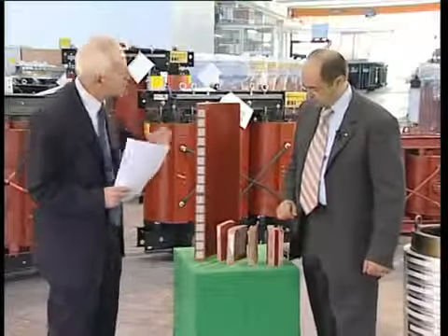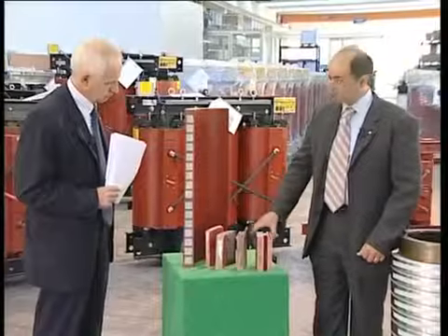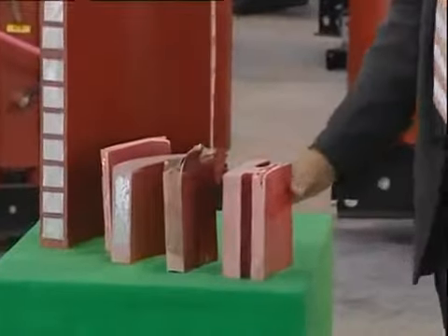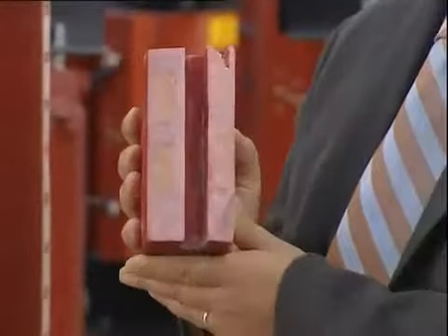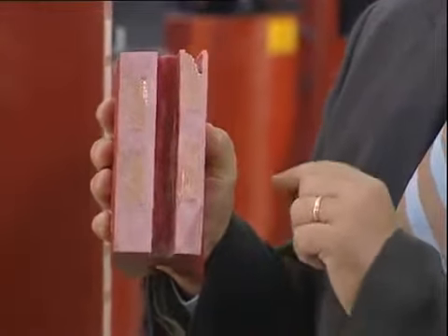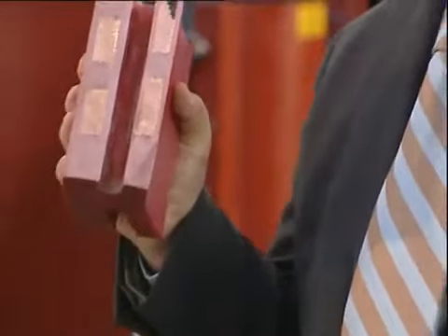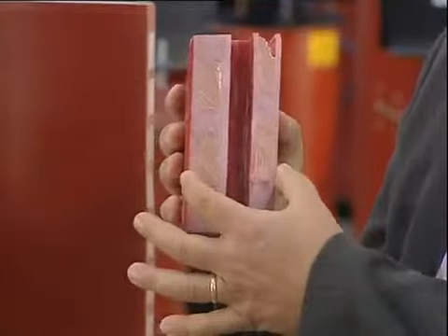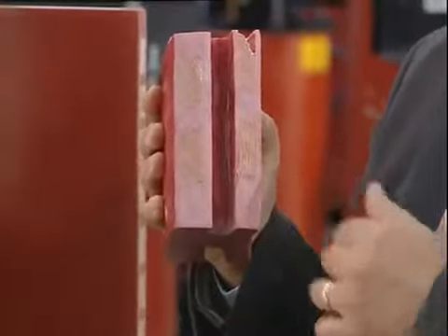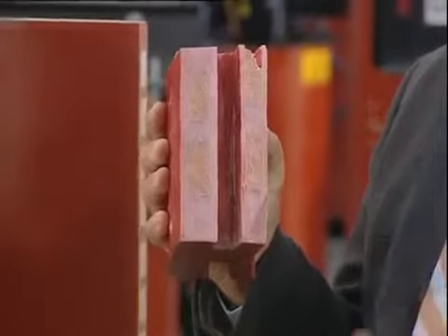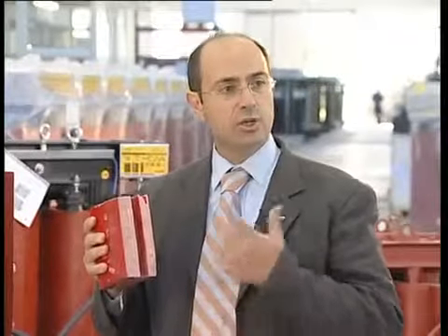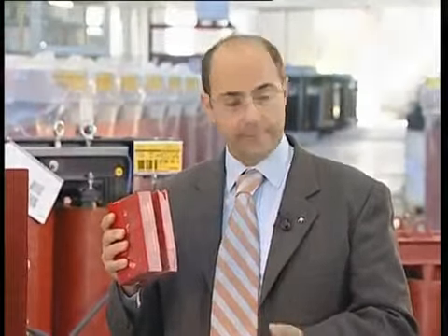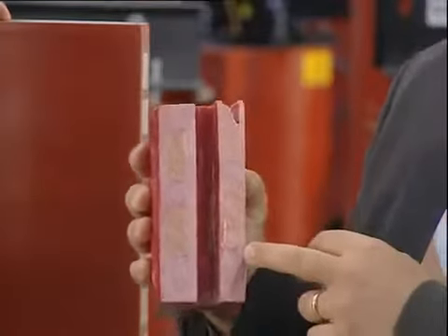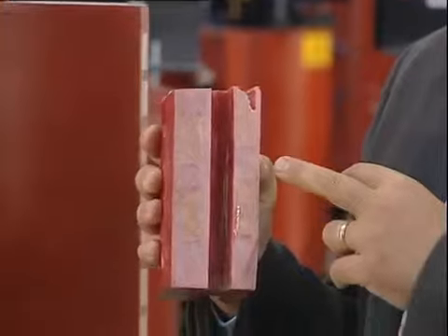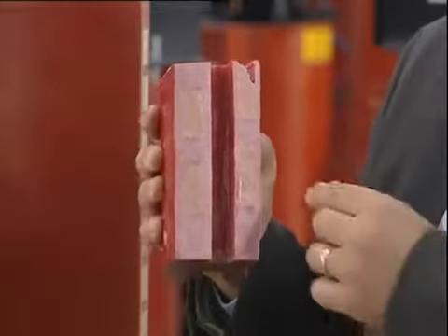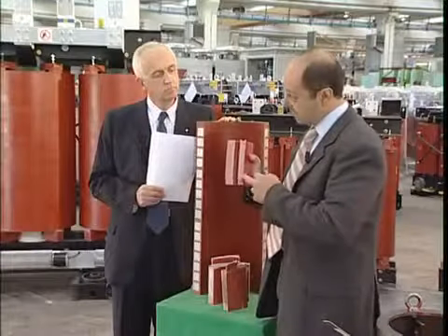What happens, on the other hand, on windings by other manufacturers? Let us take any two very common types of winding. Let's start from the first, which is the typical discs winding, in which winding sections are shaped as discs. This type is similar to one of our windings, with the exception that in one single disc, the turns are not arranged one on the other radially, with a continuous and constant potential difference, but they are layered, and each layer can include some dozen turns. This implies that the turns on one same layer have the same dielectric stress as one of our windings, but those in adjacent layers, i.e. arranged in the radial direction, do not.